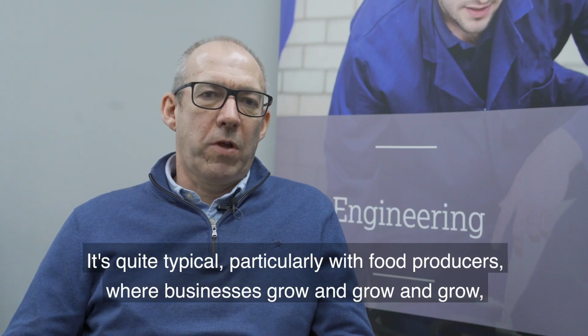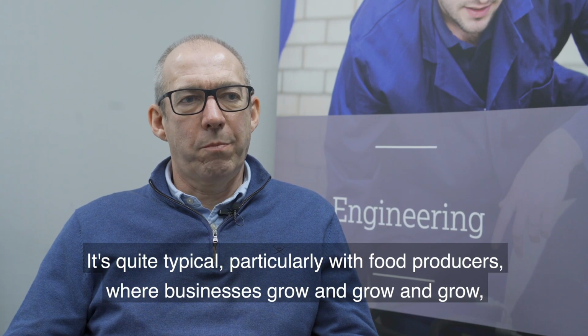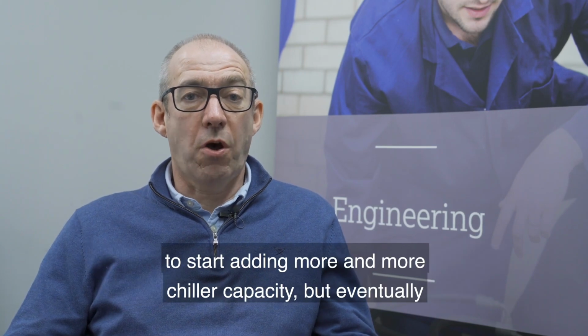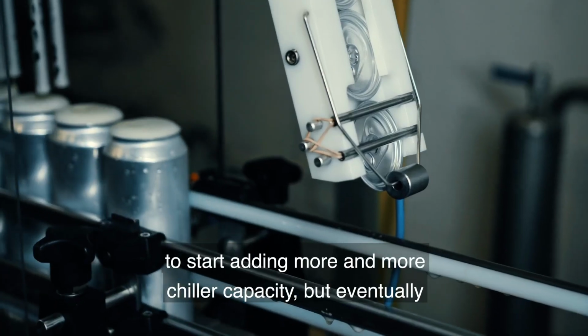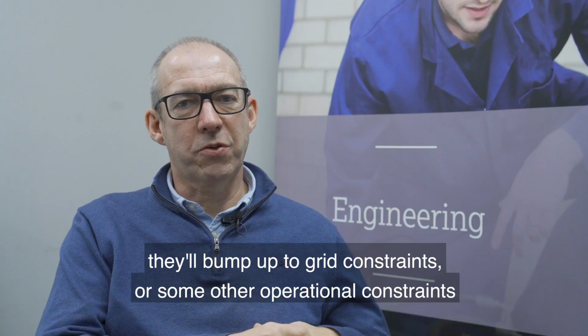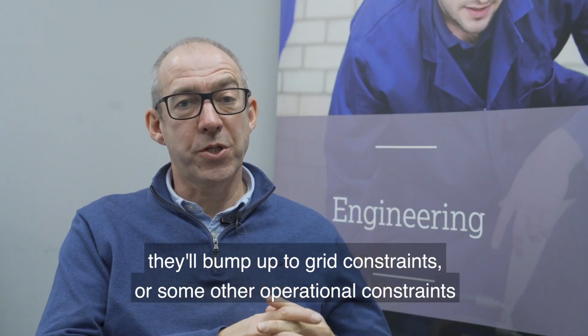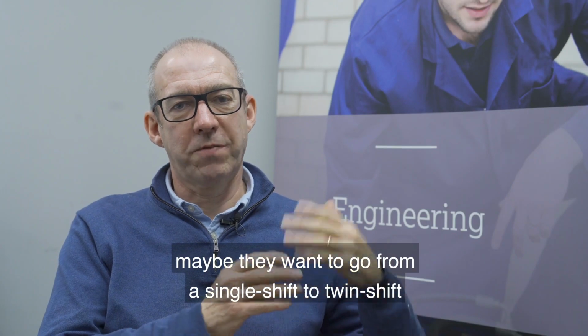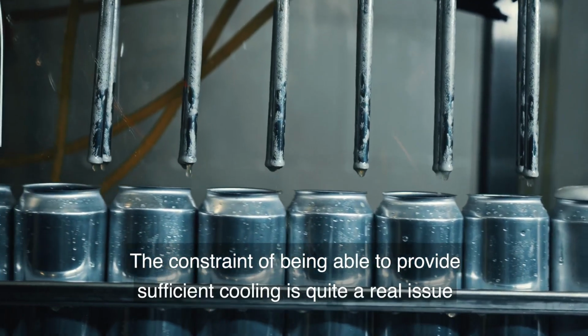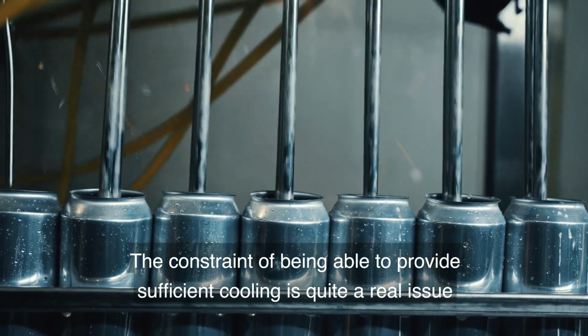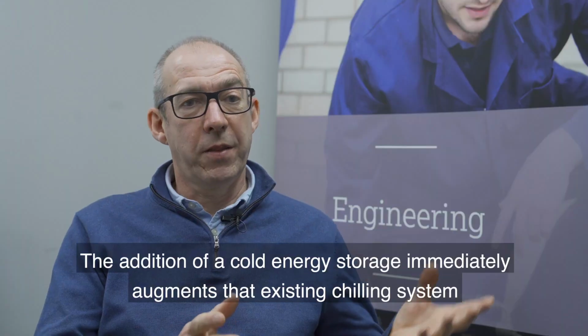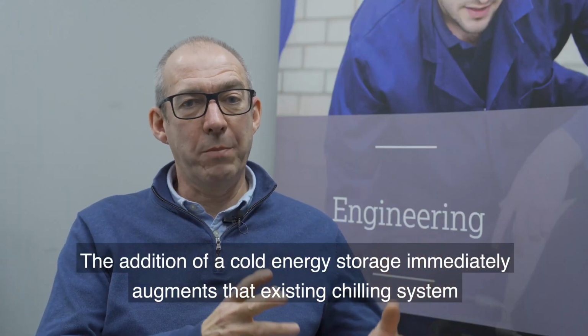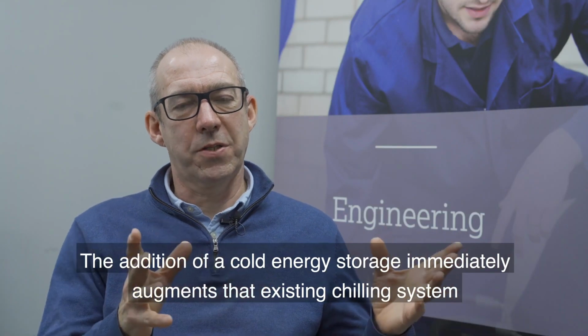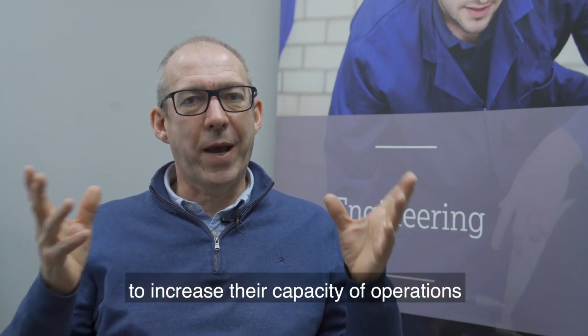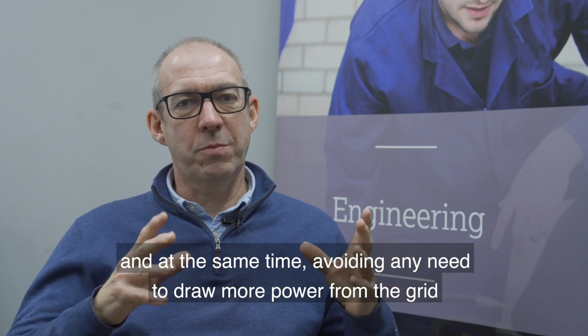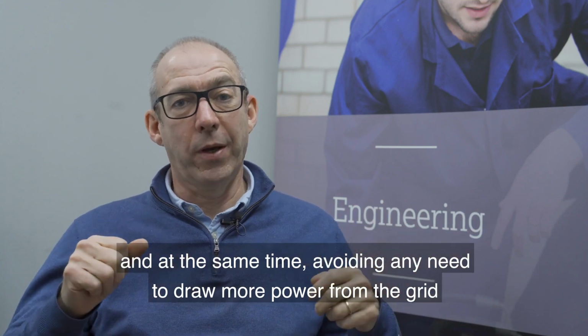It's quite typical, particularly in food producers, where businesses grow and grow and start adding more and more chiller capacity, but eventually they bump up against grid constraints or other operational constraints. Maybe they want to go from a single shift to twin shift. The constraint of providing sufficient cooling is a real issue that stops that business growing. The addition of cold energy storage immediately augments the existing chilling system to increase their capacity of operations, at the same time avoiding any need to draw more power from the grid.